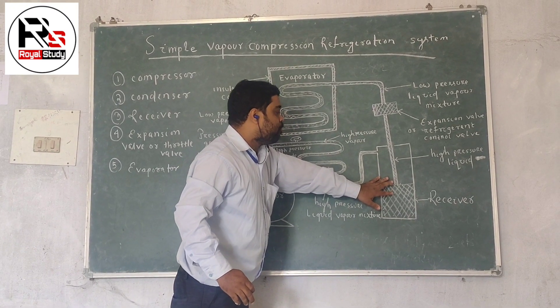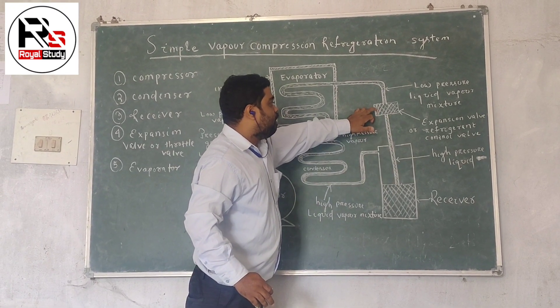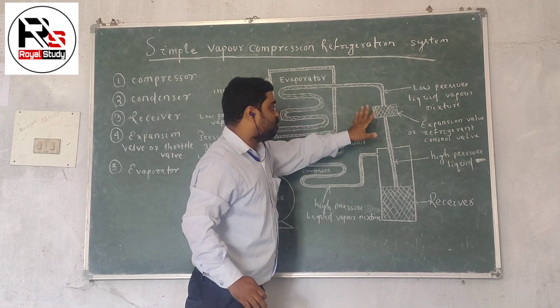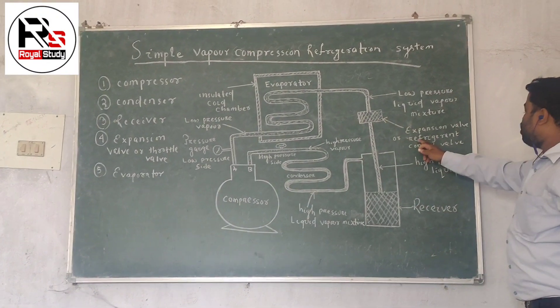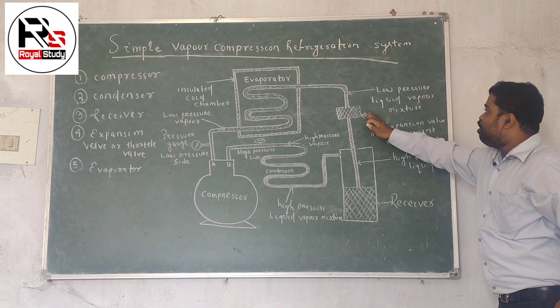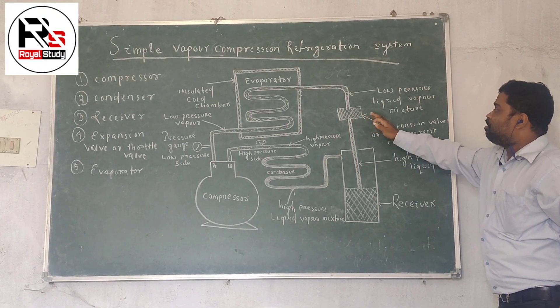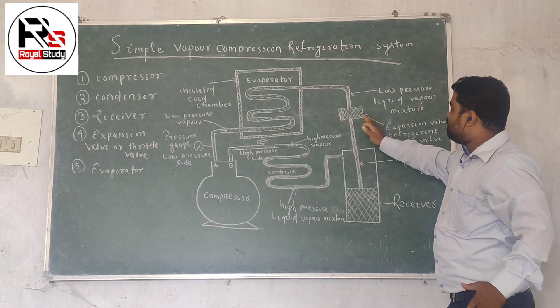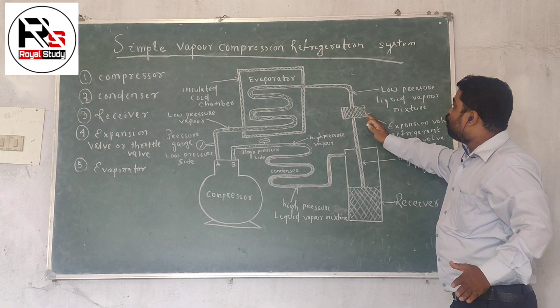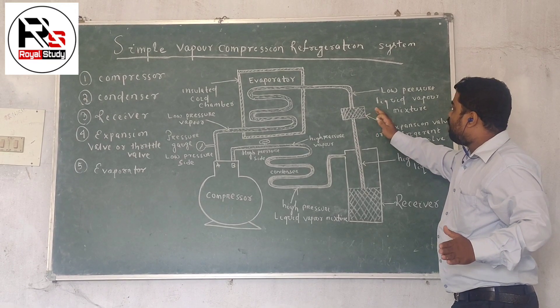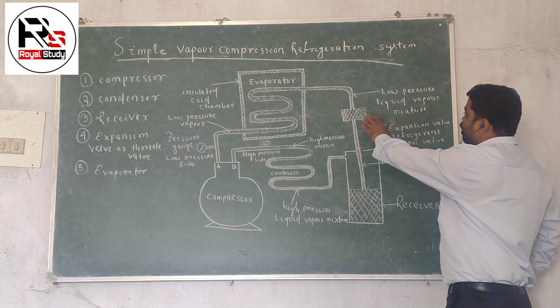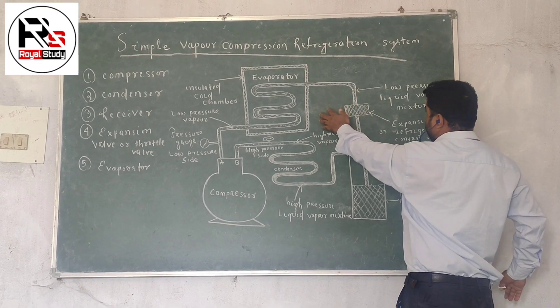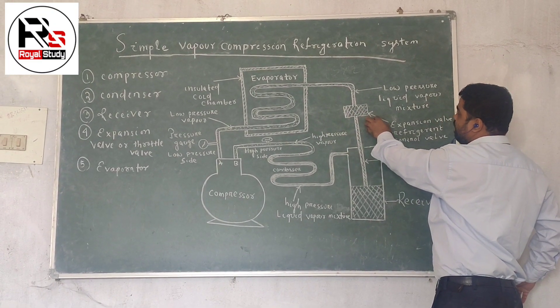When it is stored in the receiver, then it comes to the expansion valve. The high pressure liquid goes to the expansion valve. The expansion valve is also known as a refrigerant control valve. The main function of the expansion valve is to control the high pressure liquid refrigerant at a controlled rate, in order to reduce its temperature and pressure. After reducing temperature and pressure, it comes to the evaporator.